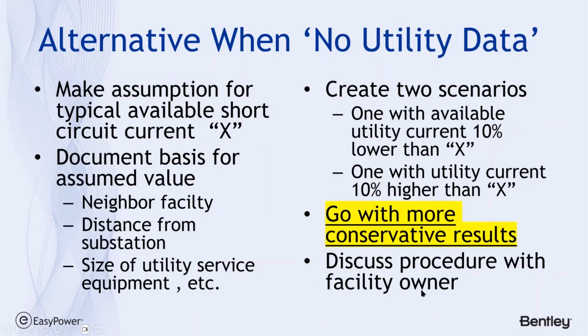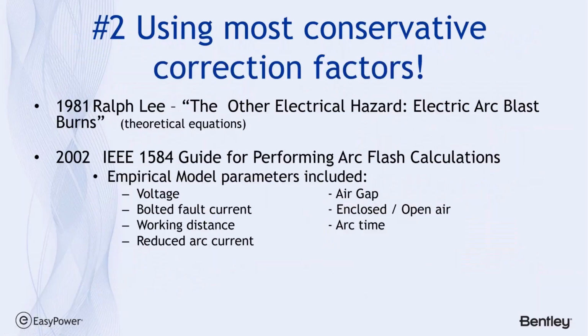The main thing that you want to do is document your path, whatever you did to make those assumptions. Now, this goes to being conservative in the selection of correction factors. In the new 2018 model of 1584, there's a number of correction factors that you can use, either the typical value, which is included in the standard and included in EasyPower, or if you know some value or you want to estimate a worst case on one of these, you can input that data yourself as user specified.